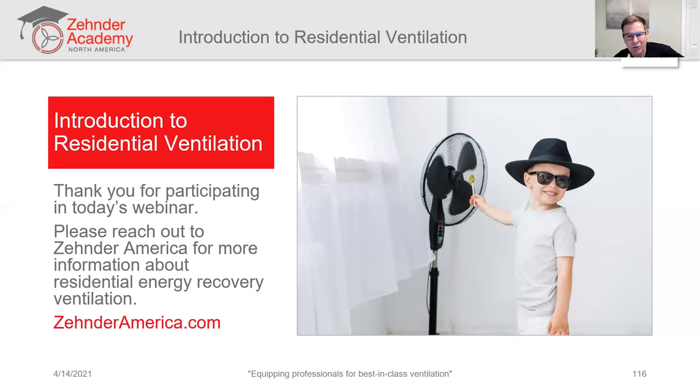But just as an example, that ComfoAir 350 that you're asking about, 218 is the max speed. We usually will design the system with a ComfoAir 350 to run at about half of that speed. So usually you're looking at somewhere in the 100, 120 CFM range as the normal operating speed. From there, they can even go into low speed or into away mode. Most of the ventilation codes only require these ventilation rates when the building is occupied. So you could theoretically turn the system off when it's not occupied and still be meeting code. We have away mode, which is just a very slight trickle of air through the system. Low speed is somewhere in between there and the normal speed, which again, for the 350 is maybe around 100, 120 CFM. And then that extra, up to 200 or 218 or whatever, typically will be reserved for boost mode.